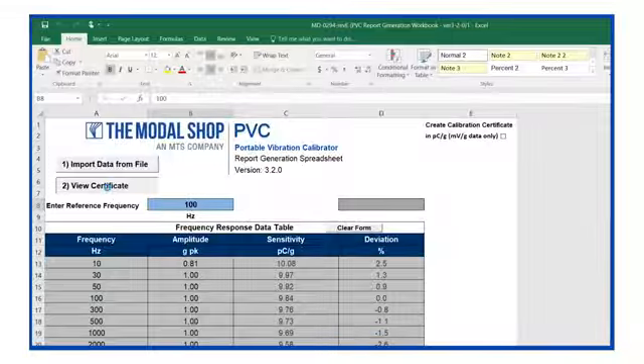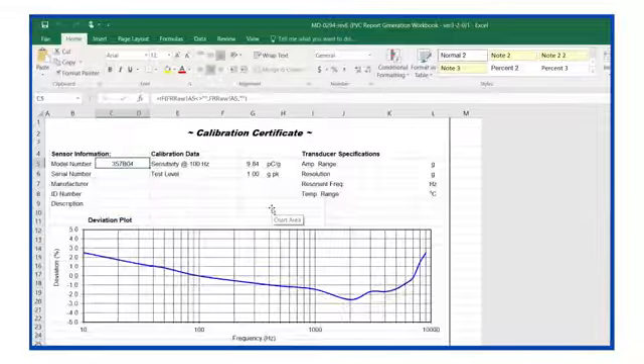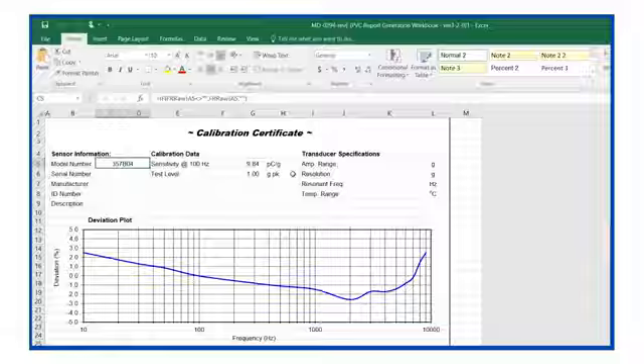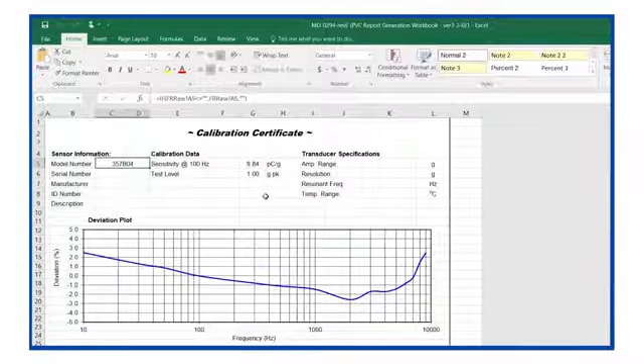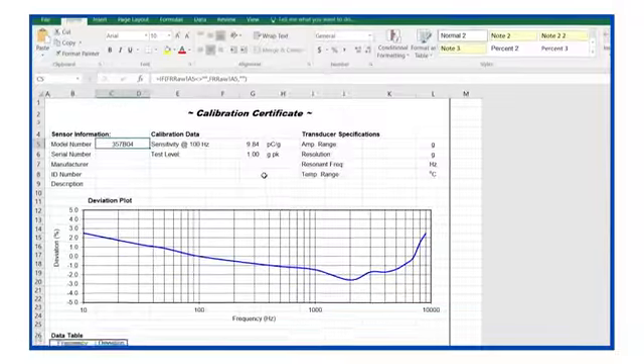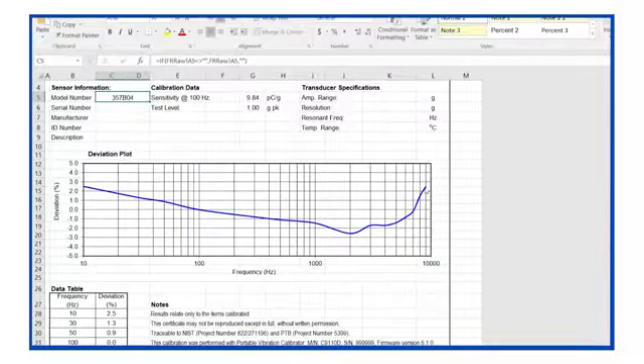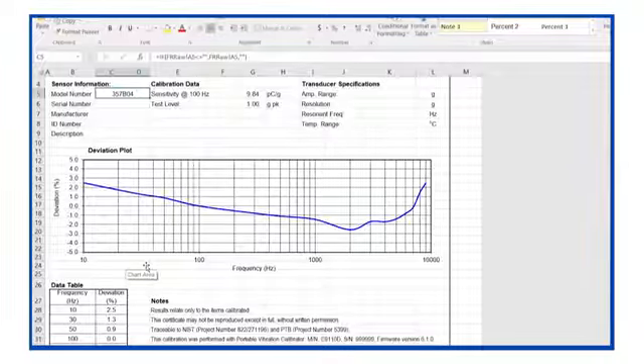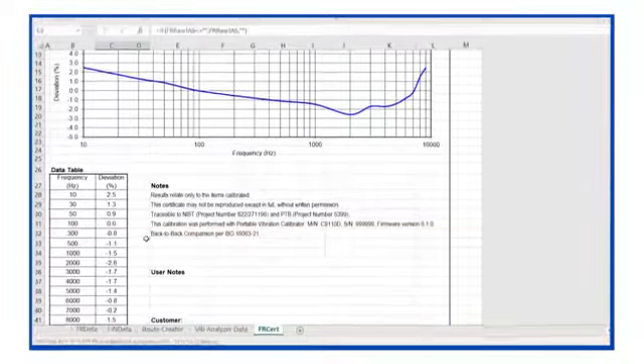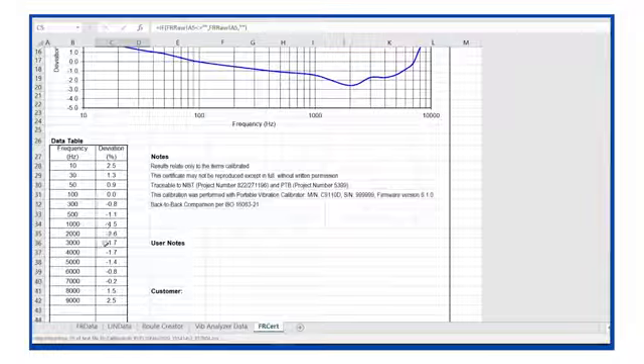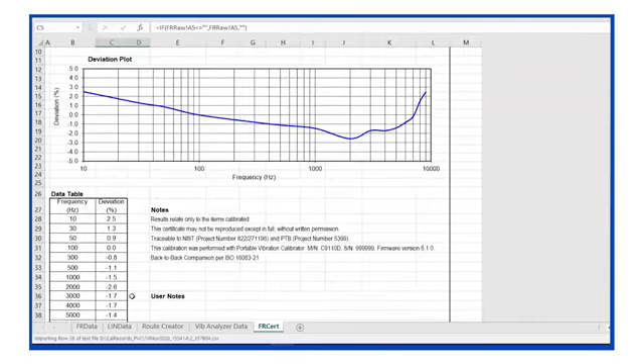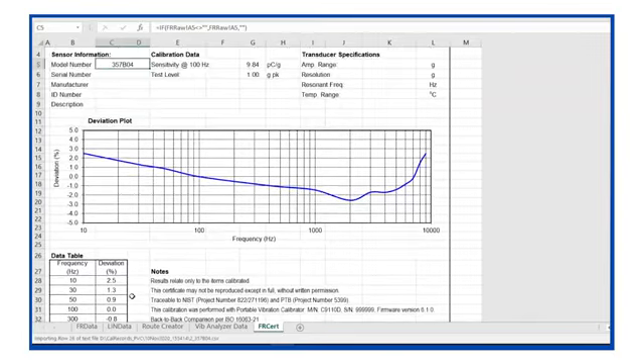Next step is to hit View Certificate, and this is my calibration certificate for the 357B04. Sensitivity at 100 Hertz of 9.84 picocoulombs per G, and a test level of 1G peak. Now your eye is immediately drawn to the calibration line, which doesn't look super great. But what happened is the worst deviation that I had was 2.6% down at 2000 Hertz. And I also had 2.5% high at 10 Hertz and 2.5% high at 9000 Hertz. All of these points passed calibration. They needed to stay within plus or minus 5% of the sensitivity at reference.